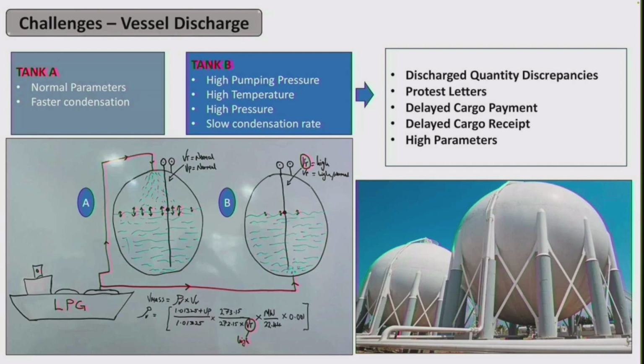As your gas is showering, you definitely have dead stock. Remember, you had an empty tank with vapor at around 30-something degrees. So you want that vapor to come back to liquid, because it's a huge amount of vapor. One way or another, it has to come back, because as you're pumping in, it's compressing, so some of it has to return to liquid. If it's showering from the top, you have the opportunity to cool down this product and make this phase change very fast, and you can see the reflection of this phase change very easily.